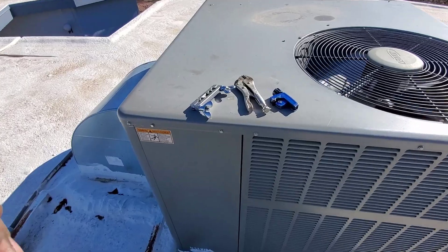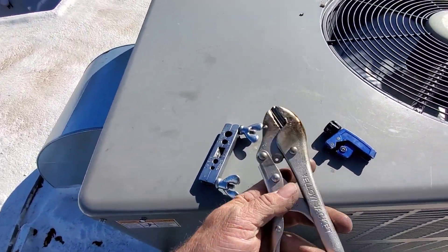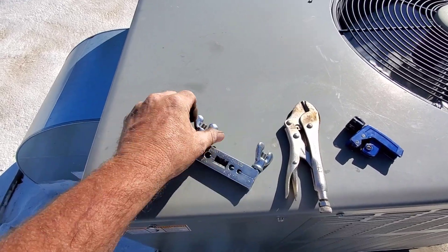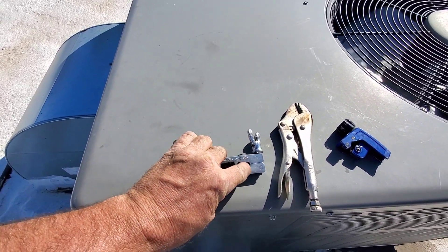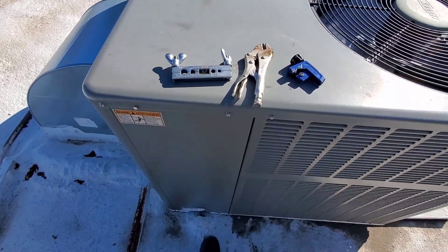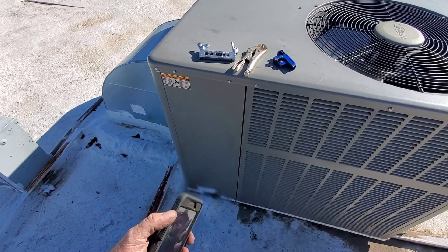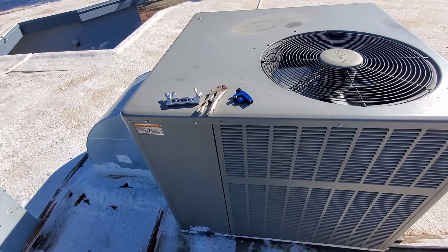All wrapped up. Pinch-off tool saved the day again. I like using this one real quick — you can use this to pinch also. You've got to crank these down. But these are what you use to round it back out. Now that little stem that comes out of there was not a true quarter inch, so I was only able to round it back out just a little bit. It's 4 o'clock — I got here almost at 3 o'clock, so it's a little over an hour.